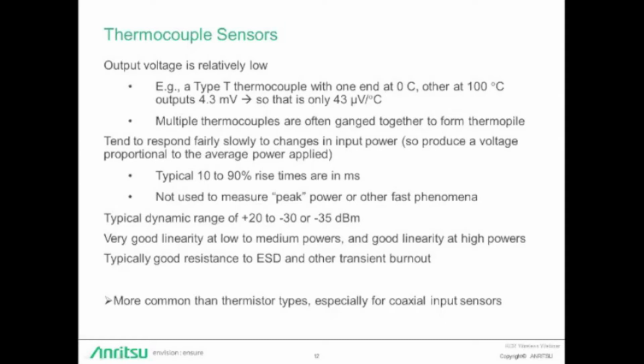Thermocouples have a typical dynamic range of -20 or +20 to -30 or 35, which is a little wider than your typical thermistor-based sensor. They have very good linearity at low powers and good linearity at high powers. Typically, thermocouples have good resistance to ESD and other transient burnout, making them more robust than thermistors. So for all the reasons above, thermocouple sensors are more common for regular use than thermistors. Thermistor sensors are common for cal labs. So the challenge in general for thermal sensors is that they're relatively slow and have a limited measurement range.